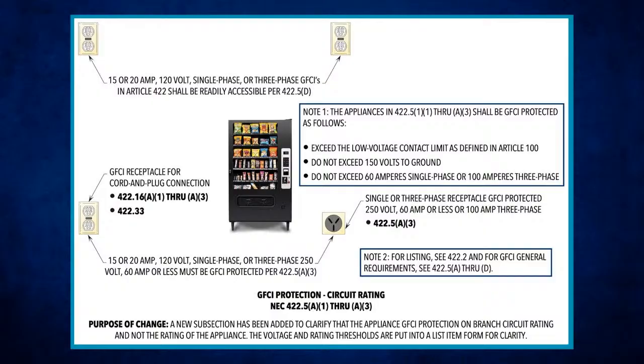We talked about this before, but when you go over and look at 422, they made a few different changes than what we were expecting. When you look at the general requirements for appliances that are 150 volts or less to ground and 60 amps or less, single or three phase, what are they required to be provided with? Class A protection. The thing I like to point out is there's a sentence that says multiple Class A protection devices shall be permitted, but shall not be required.